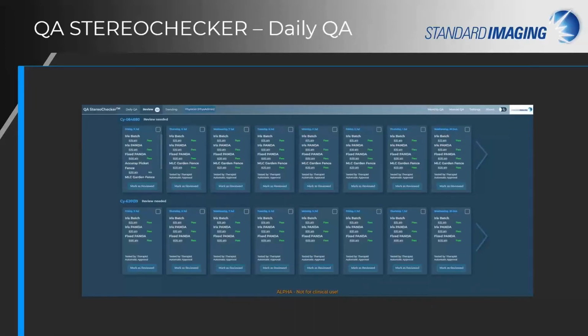Review tickets are brand new to the software. These tickets provide the daily QA summary results for review and sign-off by an authorized physicist. Individual or multiple tickets may be marked as reviewed, with an opportunity for the reviewer to add additional comments that become part of the report and permanent record. If any alerts or errors are noted on the ticket, the timestamp is a link back to the daily results where you can review the image and the results in more detail.